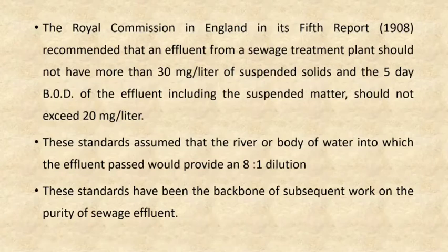The Royal Commission in England, in its fifth report, recommended that effluent from a sewage treatment plant should not have more than 30 milligrams per liter of suspended solids, and the 5-day BOD, biochemical oxygen demand, of an effluent including the suspended matter should not exceed 20 mg per liter.